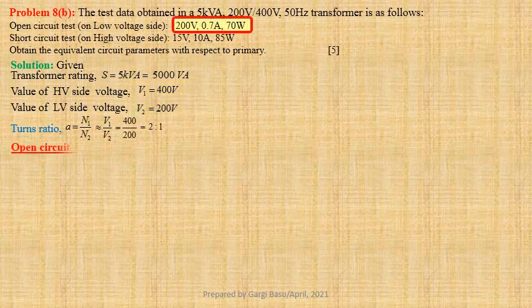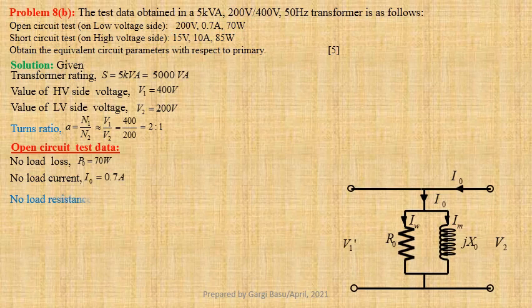From open circuit test data, we get no load loss P0 equals 70 watt. No load current I0 equals 0.7 ampere. No load resistance R0 equals V2 square divided by P0. Using values we get 200 square divided by 70, that gives us 571.4286 ohm.